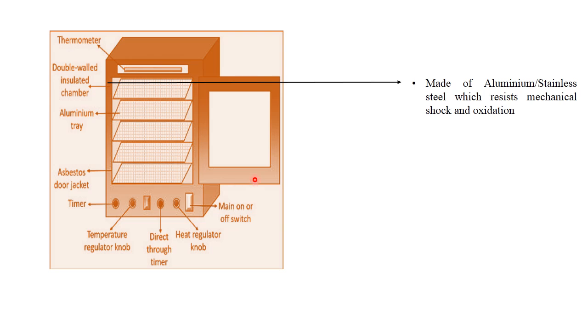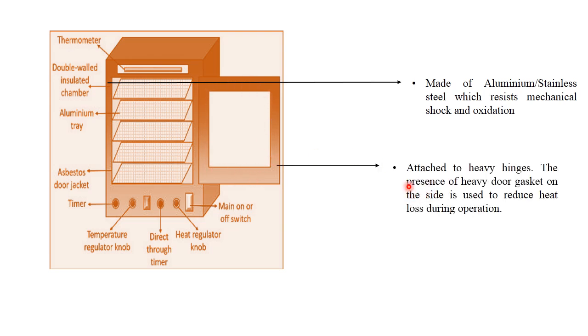Now this is the door of the hot air oven. This door is attached to heavy hinges. The presence of a heavy door gasket on the side is used to reduce heat loss during operation. This gasket is made up of asbestos and it ensures that no heat is lost during the operation of the hot air oven.